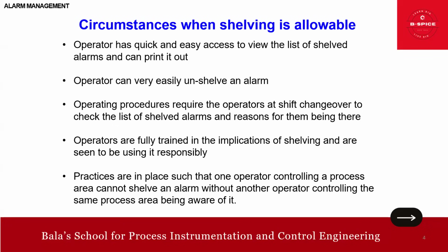To add on further, shelving is normally performed from an alarm list. Each alarm to be shelved should be individually selected. Once selected, it is acceptable to allow several alarms to be shelved as a group. It is desirable if shelved alarms are displayed on a process mimic graphic in some fairly low contrast coding that is less obvious than the normal alarms, so we can easily differentiate.